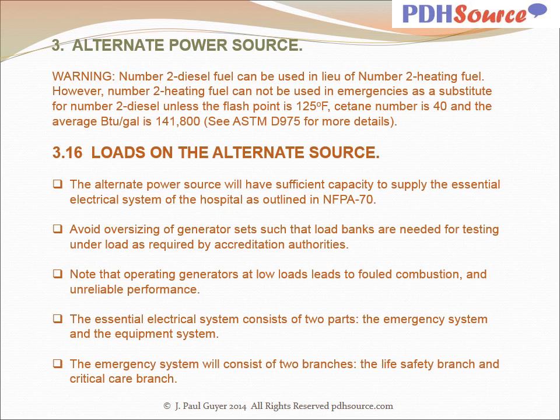The alternate power source will have sufficient capacity to supply the essential electrical system of the hospital as outlined in NFPA 70. Avoid oversizing of generator sets such that load banks are needed for testing under load as required by accreditation authorities. Note that operating generators at low loads leads to fouled combustion and unreliable performance. The essential electrical system consists of two parts: the emergency system and the equipment system. The emergency system will consist of two branches, the life safety branch and critical care branch.